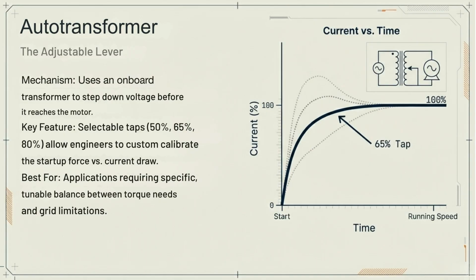The auto-transformer method uses an onboard transformer to step down voltage before it reaches the motor. Selectable taps, such as 50%, 65%, or 80%, allow custom calibration of startup force versus current draw. This method is suited for applications needing a specific, tunable balance between torque needs and grid limitations.